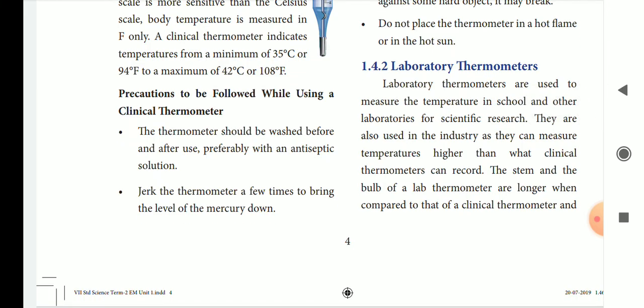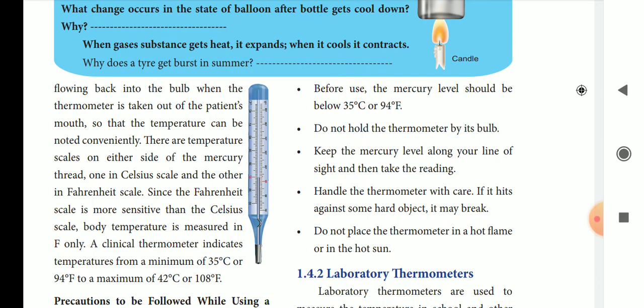Precautions: follow up for the thermometer — wash with an antiseptic solution. Jerk the thermometer a few times to bring the level of mercury down. When you go to the hospital, you can see that the mercury level is below 35 degrees Celsius or 94 degrees Fahrenheit, so the mercury level is correct. Do not hold the thermometer by its bulb. Keep the mercury level along your line of sight and then take the reading.